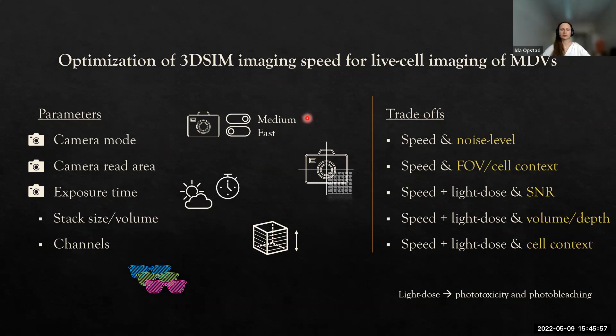Usually we image in a medium imaging speed because the noise is lower, recommended by the manufacturer, but I changed that to fast. I changed the camera read area because it takes quite a lot of time to read out all these pixels, maybe 30 milliseconds. I only used a small portion of the camera for the live cell imaging and it went a lot faster. The exposure time and illumination intensity conditions also need to be optimized to be as fast as possible, but still give a reasonable reconstruction.